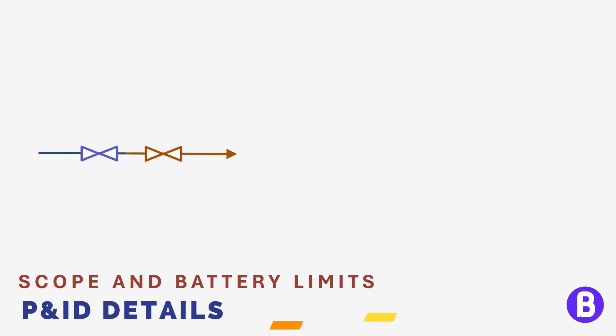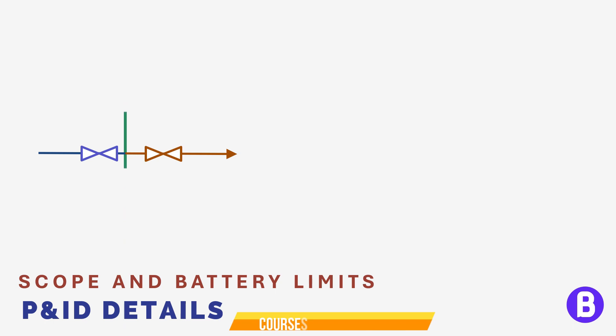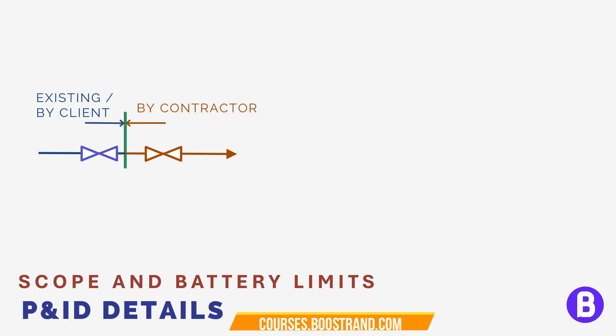P&ID should clearly define the responsibility of each part. If we see this sample pipe with two valves, we want to segregate between what is already existing and what we shall add in our P&ID. We shall draw this line separating both valves — this line shall define the scope of each part. The blue portion shall be the existing system, or what shall be supplied by the client.